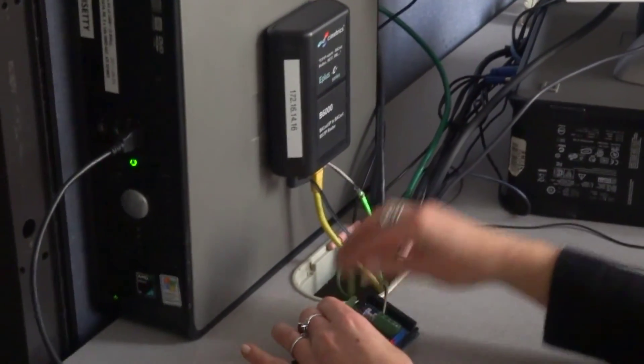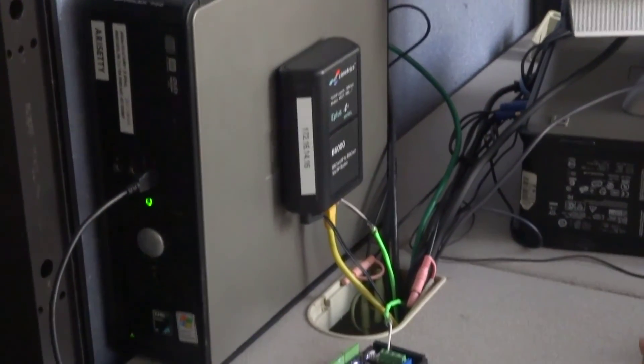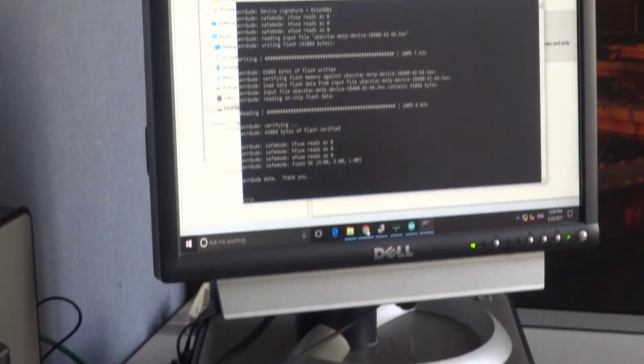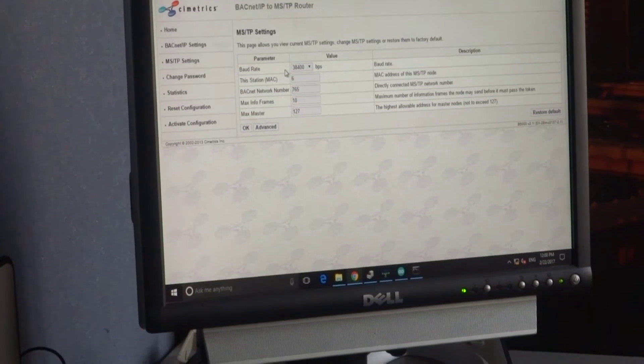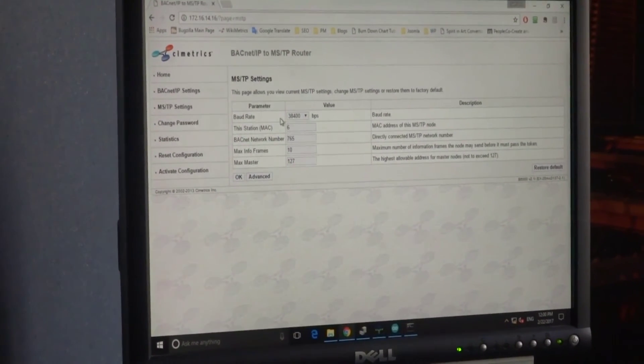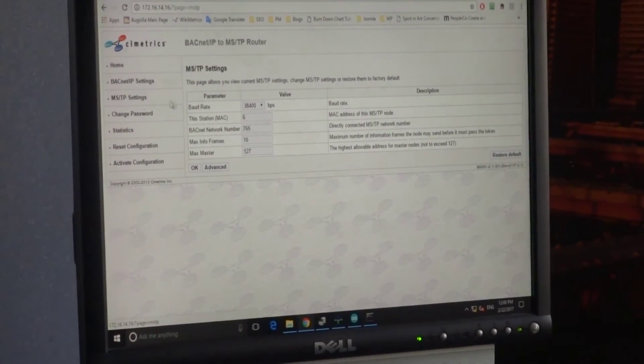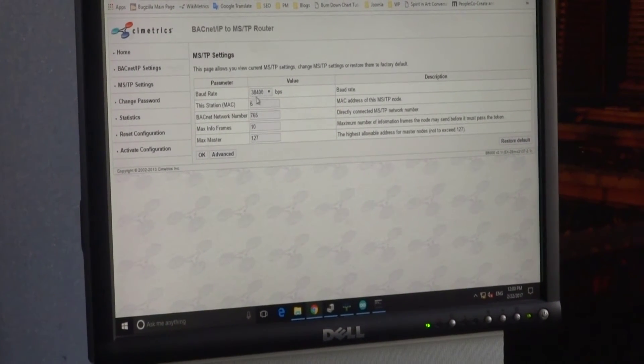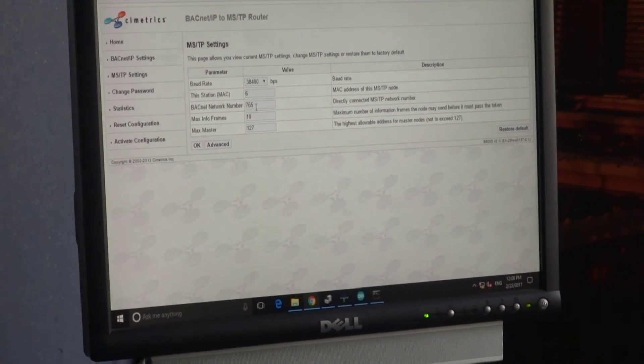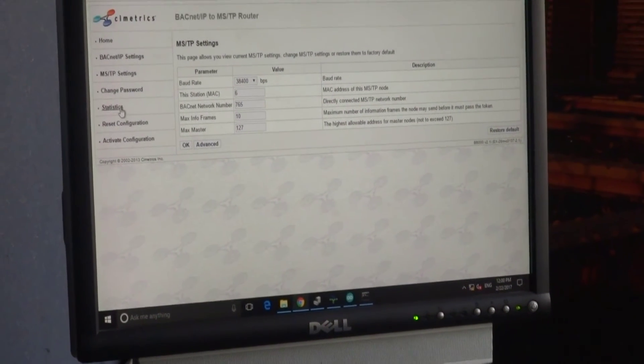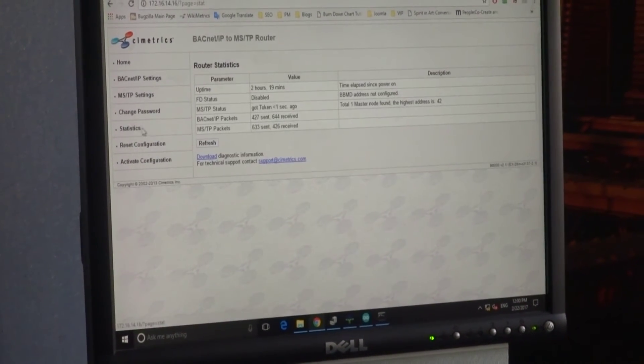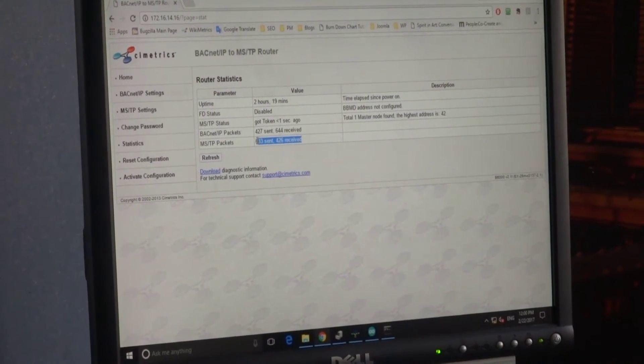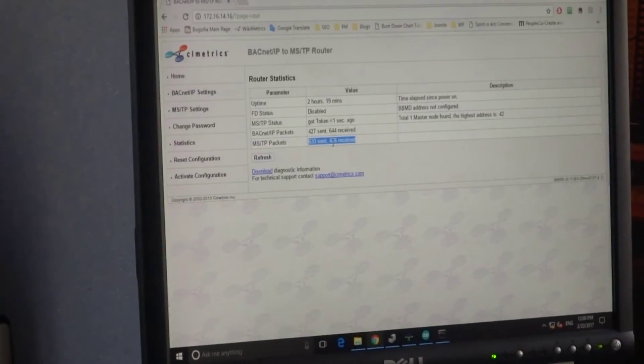And you should be able to see your device in BACnet Explorer. Let's check if B6000 can communicate with it. In MSTP settings we will make sure we specify the correct baud rate and other parameters. And in statistics let's see if the devices exchange MSTP packets. They do.